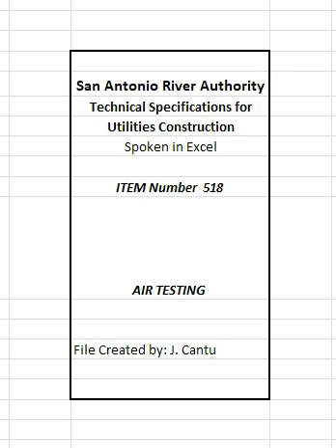Any drop in pressure from 3.5 psig to 2.5 psig greater than average back pressure of any groundwater, as required by the above table or formulas, shall be cause for rejection. The contractor must determine the cause of test failure and repair as may be required to accomplish a successful air test. Tests over individual joints or joint tests shall be performed in the same manner as stated herein, with the minimum allowable test time determined from the above table or formulas for a minimum of 10 feet of length.